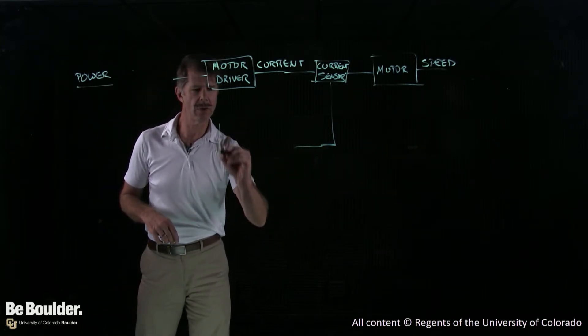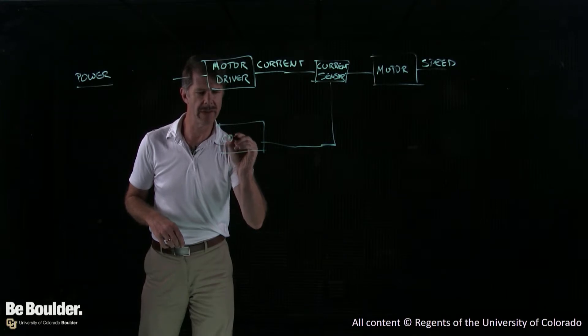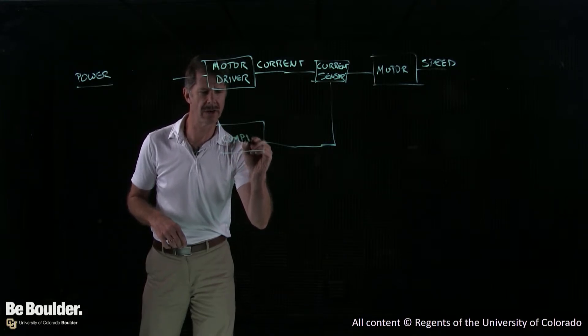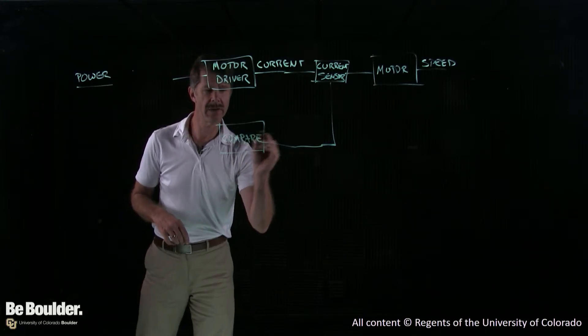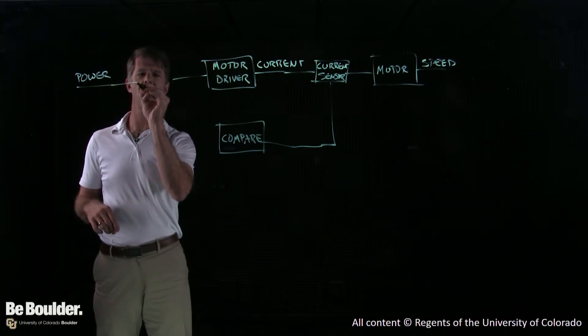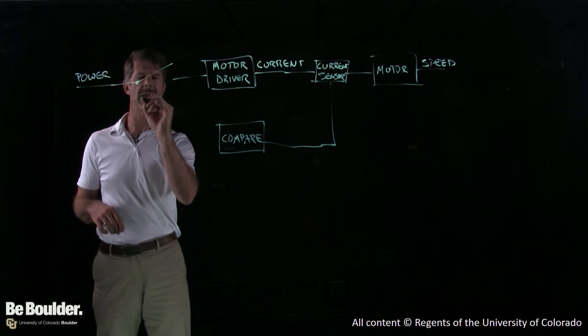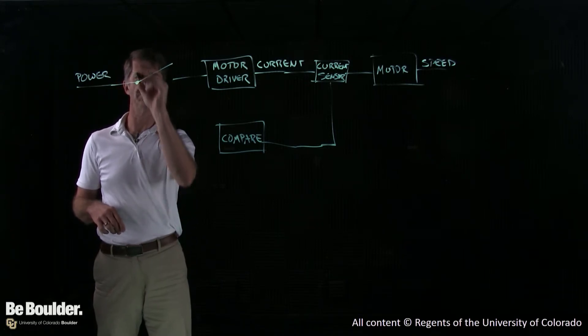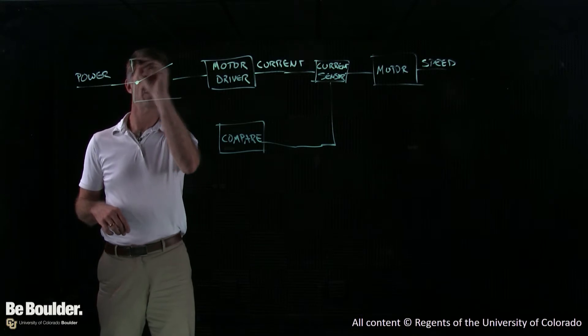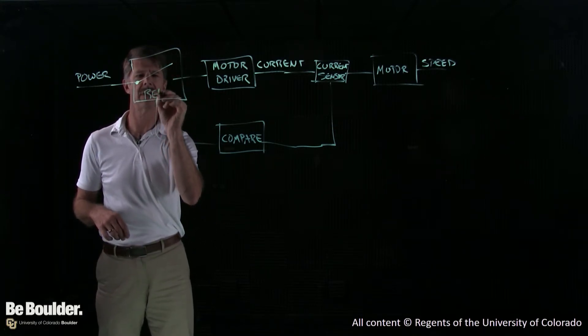So once again, you're going to put some conditioning here. Maybe you'll just call that a compare. Again, is the current higher than I'd like it to be? And we're going to do the simplest form of controller, we're going to put our relay here. So I'll just make that a box with a switch in it. And here's the control line. And I'll call that a relay.